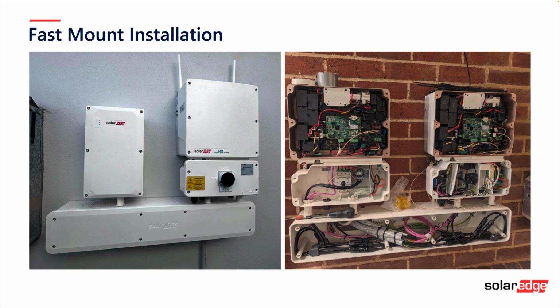The shape of the fast mount is also great because it's long and skinny. This is particularly handy, as you can see in the diagram on the right, there are quite a few sets of branch connectors inside the box. This comes in handy because as you install SolarEdge batteries onto existing systems, you may have inherited DC cable runs coming down to the ground, with 2, 3, or 4 cables that need to be paralleled easily and brought into the ports on the inverter.